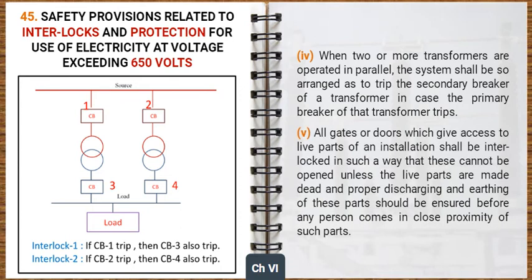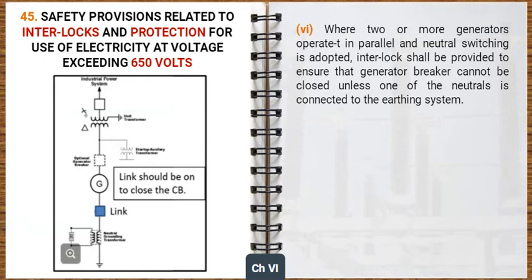All gates or doors which give access to live parts of an installation shall be interlocked in such a way that these cannot be opened unless the live parts are made dead, and proper discharging and earthing of these parts should be ensured before any person comes in close proximity of such parts. Where 2 or more generators operate in parallel and neutral switching is adopted, interlock shall be provided to ensure that generator breaker cannot be closed unless one of the neutral is connected to the earthing system.